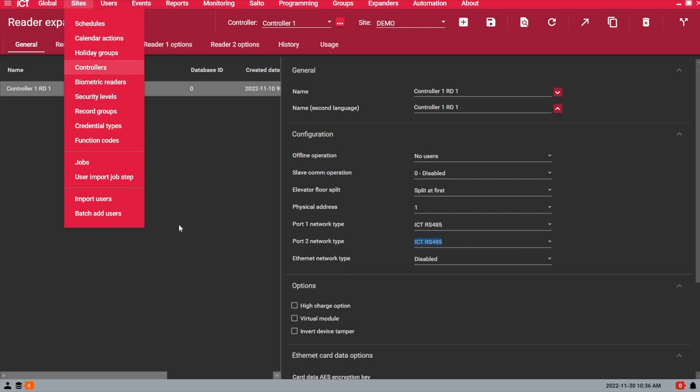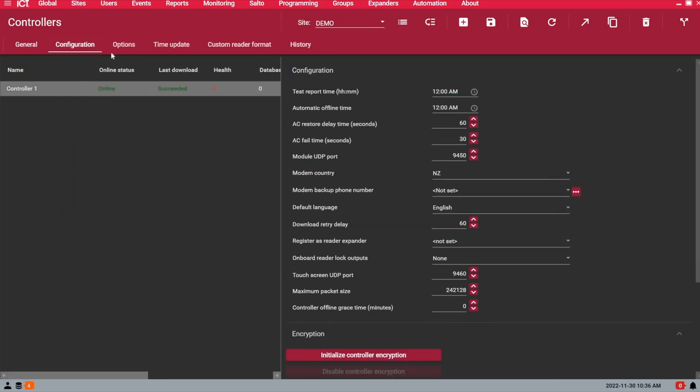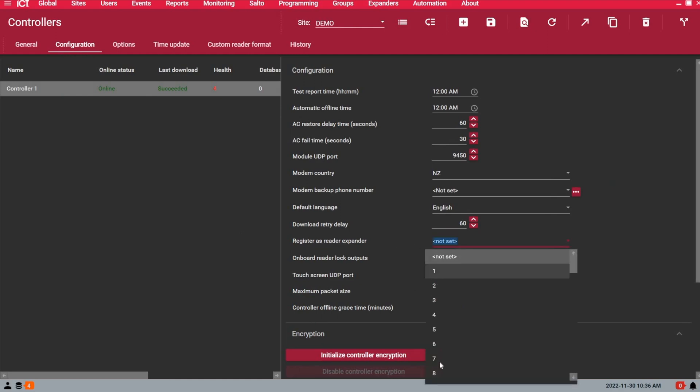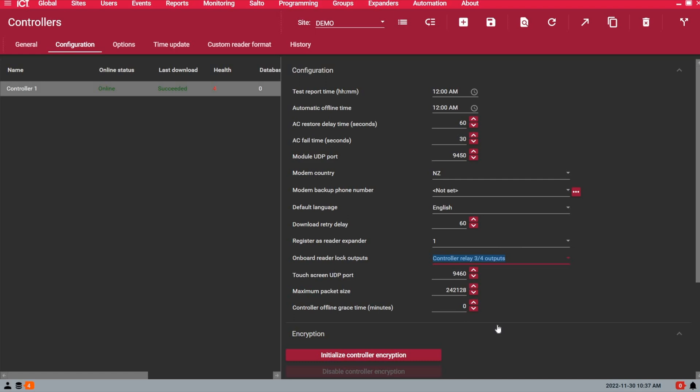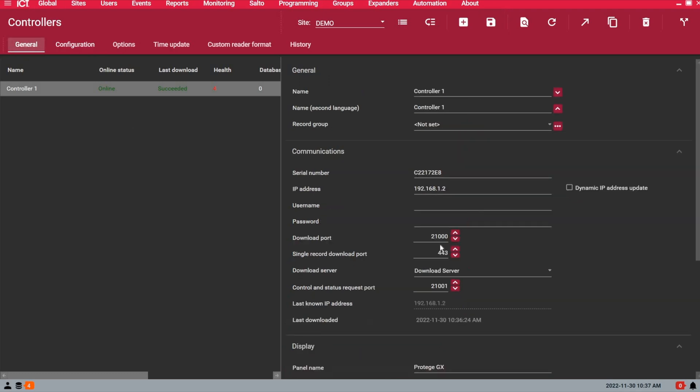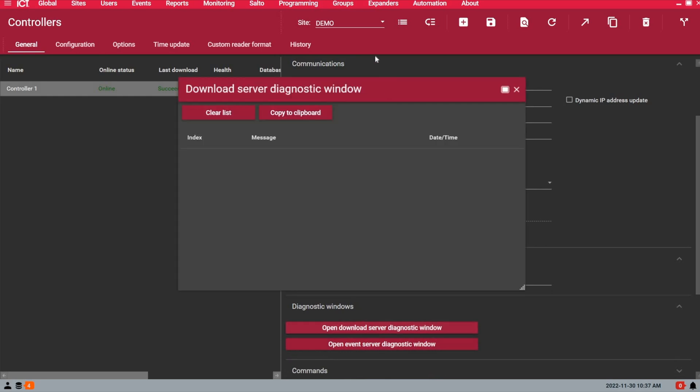So under sites, controller, under the configuration tab, I want to enable the reader expander as address 1. And the lock outputs will be reader 3 and 4 on the controller. So in other words, controller reader 3 and 4. These are the dry contact relays you want to use to connect your door strike or mag lock. So again, I enable the reader expander as address 1, choose the lock outputs I want to use, I save.